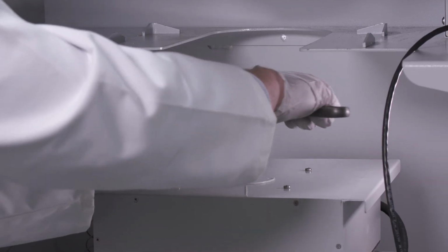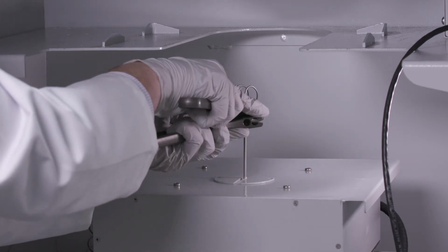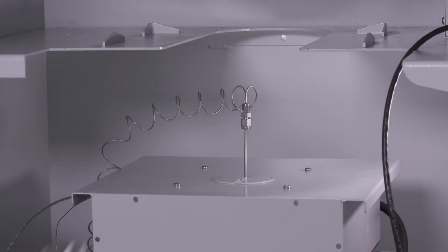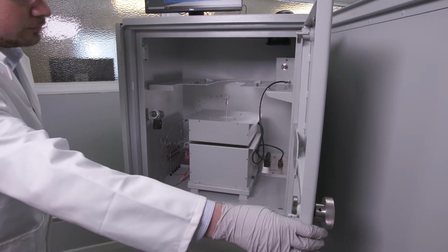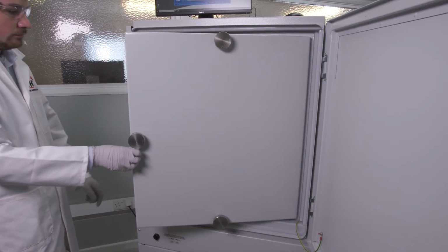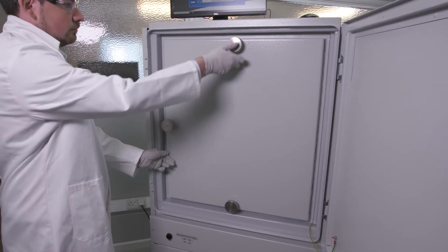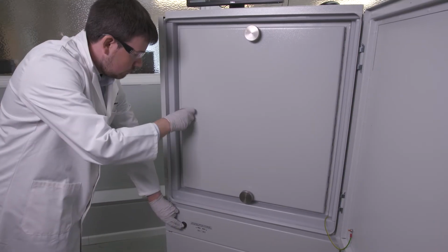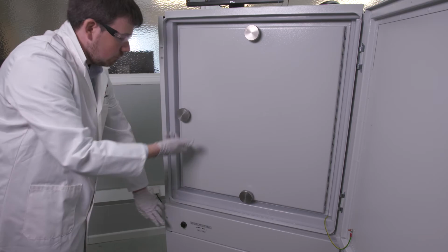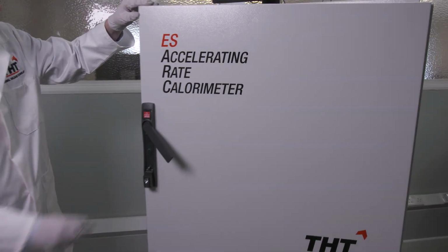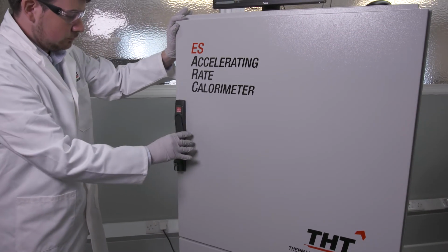Make sure that the pressure tube is attached to the top of the calorimeter. Close the inner door using the door lock button and the locking wheels. Lock the outer door using the handle. Push the handle into the locked position.